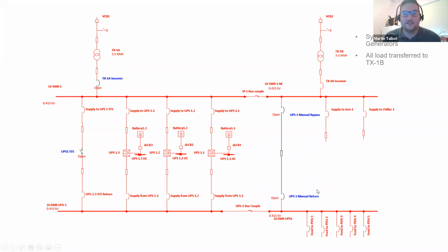And what I'd always advise is that you set up your safe system of work in respect to arc flash to always have the worst case scenario considered. So as Marcin said, it's going to be a UPS bypass. It might also be from generators, and that will be your set level. The worst case will always be what you set your safe system of work to.